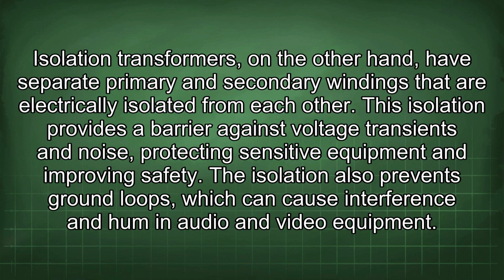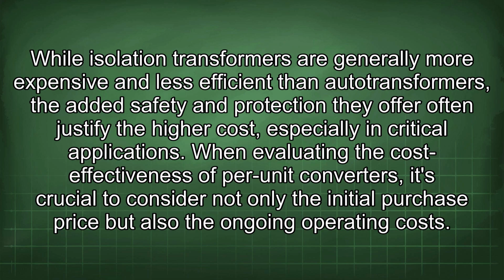Isolation transformers, on the other hand, have separate primary and secondary windings that are electrically isolated from each other. This isolation provides a barrier against voltage transients and noise, protecting sensitive equipment and improving safety. The isolation also prevents ground loops, which can cause interference and hum in audio and video equipment. While isolation transformers are generally more expensive and less efficient than autotransformers, the added safety and protection they offer often justify the higher cost, especially in critical applications.